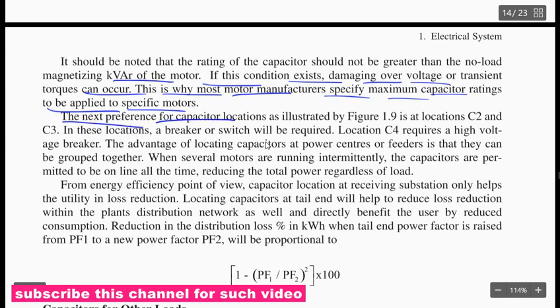The next preference for capacitor location, as illustrated in the figure at locations C2 and C3, requires breakers and switches. Location C4 requires a high voltage breaker. The advantage of locating capacitors at the power center or feeder is that they can be shared when several motors are running intermittently.